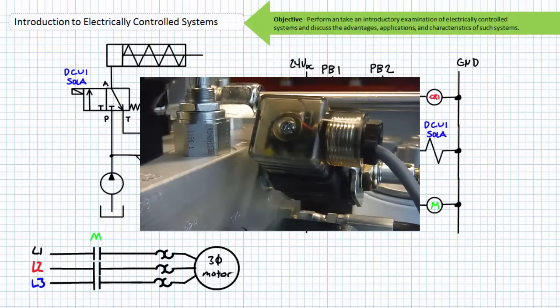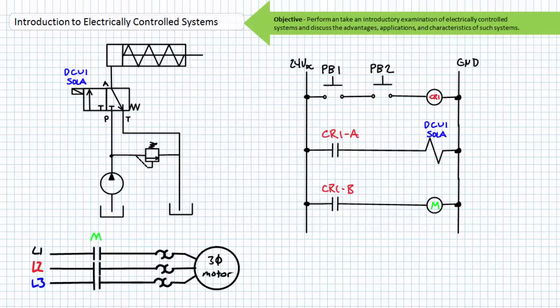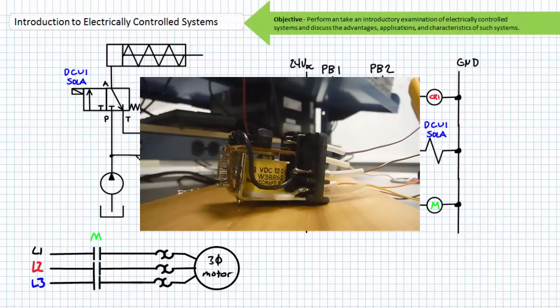Solenoid-operated valves typically have a pilot light associated with the solenoid, which allows an operator or technician to verify if the solenoid is being energized. Additionally, the valve being a physical device that shifts position, one should be able to hear or feel movement. The relays themselves are again physical devices. One should be able to see the coil being energized, and when the coil is energized, those associated contacts should change to their opposite states.